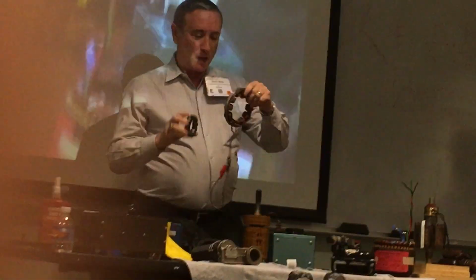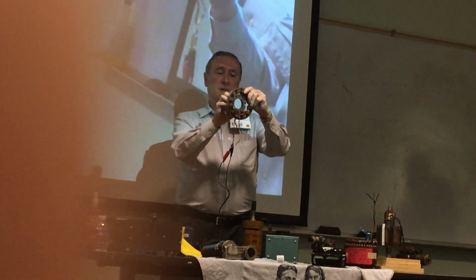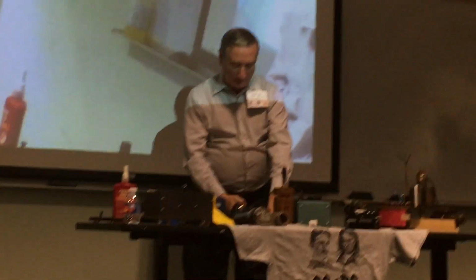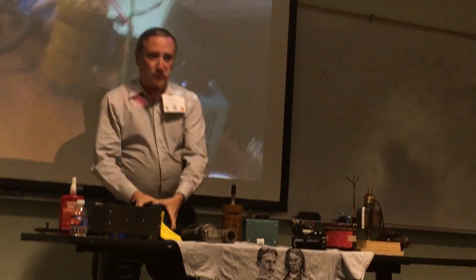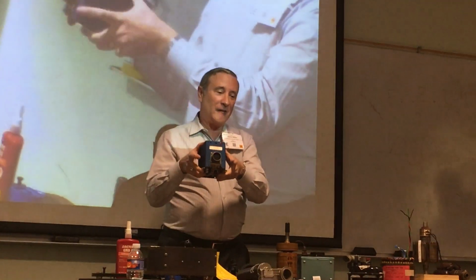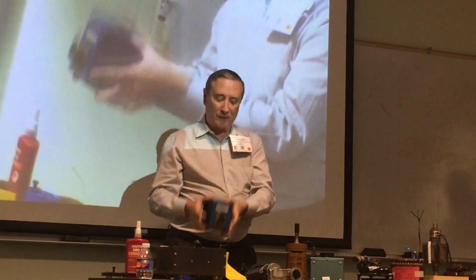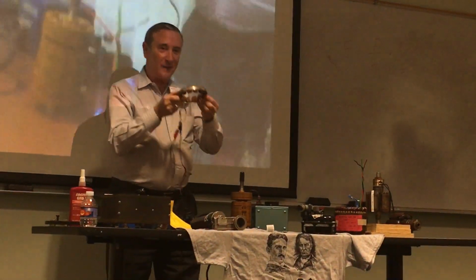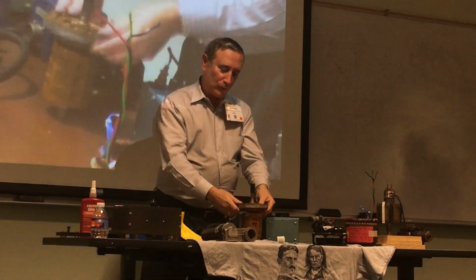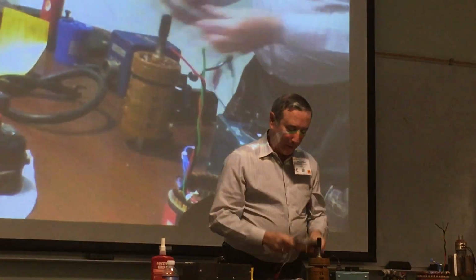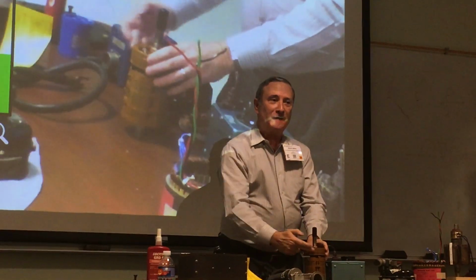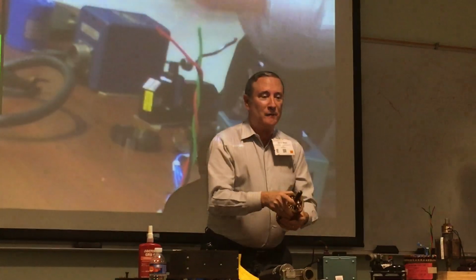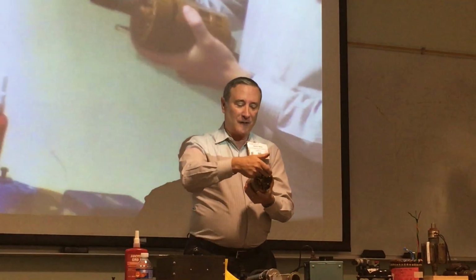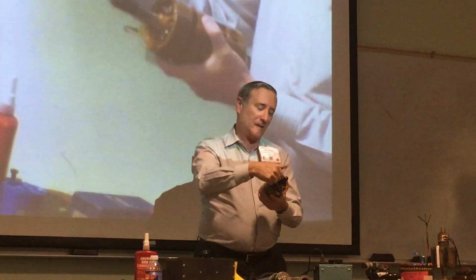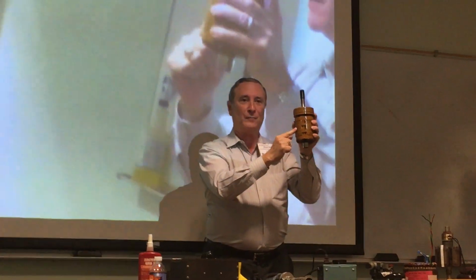This small magnet puts out about 21 volts AC out of its corresponding stator. This is the stator, and it rotates inside it. You get an AC voltage coming out of it. That small voltage goes to the voltage regulator. The regulator takes that small AC voltage, turns it back into DC with diodes, and feeds it back into the second stage exciter, which fits over the rotor. So while this is turning, you now have an AC voltage being generated in the top of the rotor. That's the second stage. What's really brilliant is they put diodes in the rotor, so now you have that small AC voltage turned back into DC, and that's fed into the main section of the bottom of the rotor.